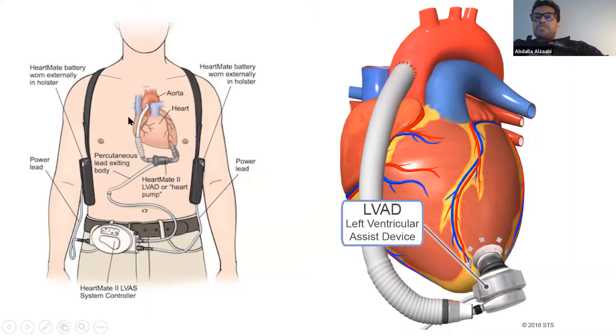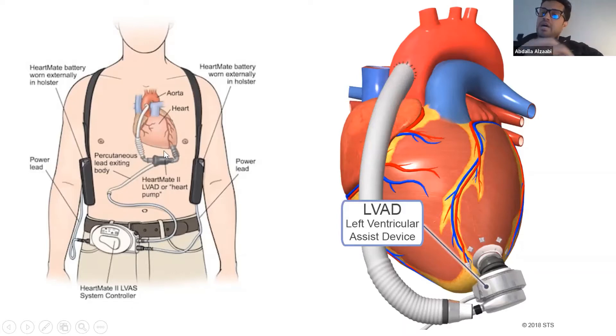You have the pump and a percutaneous lead known as the driveline, which is connected to an outside controller. The controller is connected to two batteries that provide external power for both the controller and the pump.